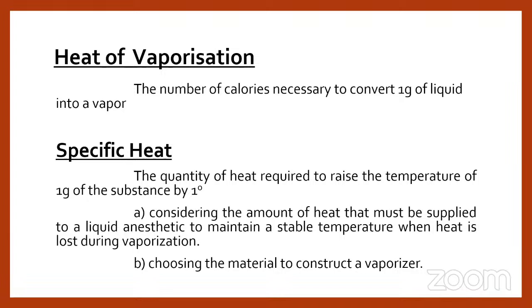It depends on two factors. The first is the amount of heat that must be supplied to a liquid to maintain a stable temperature when heat is lost during vaporization. And the second one is choosing the material to construct the vaporizer. This is very important, because whenever the liquid converts into vapor, it loses some heat due to loss of energy, and the loss of temperature will reduce the vaporization capacity of that liquid. So the container which contains the liquid has to be suitably selected to maintain the balance between the temperature and the vaporization of the liquid agent that we are using while administering anesthesia.